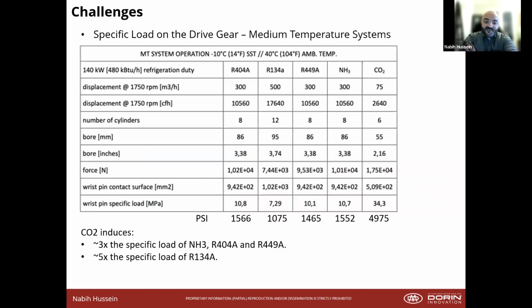Here's the PSIs you would consider for R404A. 1566 PSI would be the specific load on that wrist pin, but when you go up to CO2, it's around 5,000 PSI. And it's 3 times the load, 5 times the load, whatever it is. You plan for that wrist pin to handle that load, and if it fails, then the compressor fails.